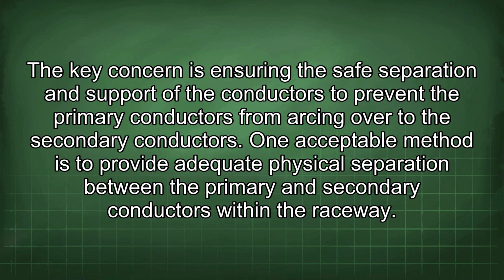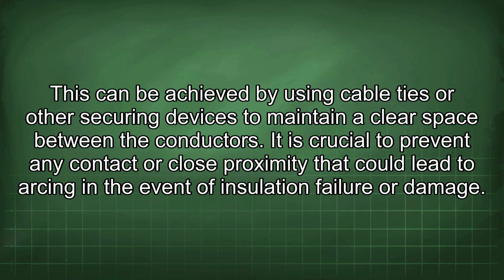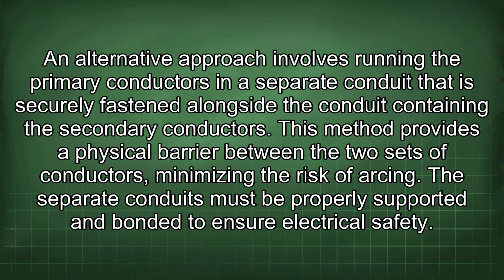One acceptable method is to provide adequate physical separation between the primary and secondary conductors within the raceway. This can be achieved by using cable ties or other securing devices to maintain a clear space between the conductors. It is crucial to prevent any contact or close proximity that could lead to arcing in the event of insulation failure or damage. An alternative approach involves running the primary conductors in a separate conduit that is securely fastened alongside the conduit containing the secondary conductors.